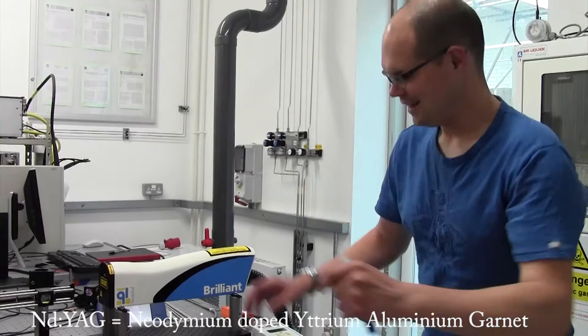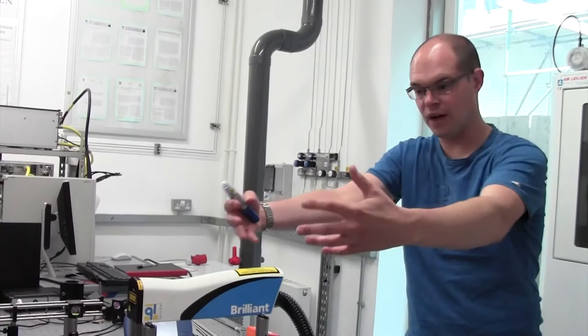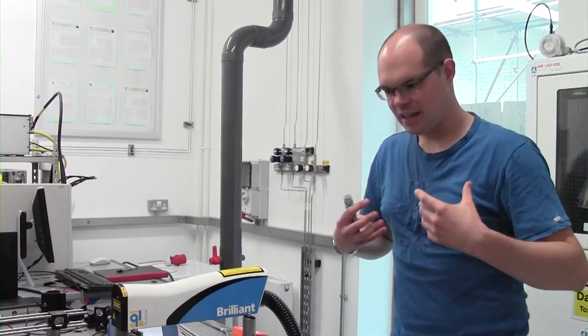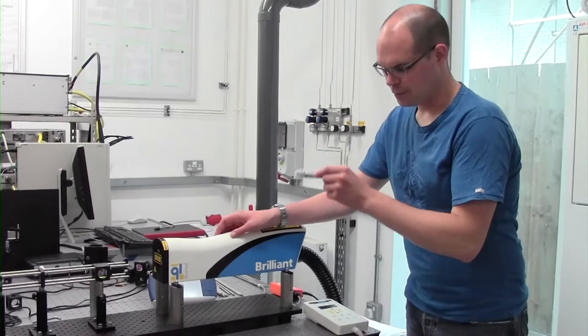What we have in here is a neodymium-doped YAG crystal. Okay. Now, that crystal has got specific optical properties. We call that optical property fluorescence. It will absorb one wavelength of light or a band of wavelengths of light. Its electrons become excited and start to jiggle, jump up a level. And then when they drop back down again, they'll give a characteristic wavelength. In this case, a YAG laser, an ND YAG laser, will produce a wavelength of 1064 nanometers.